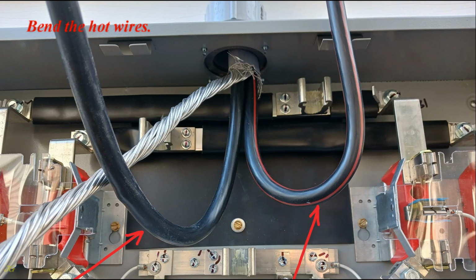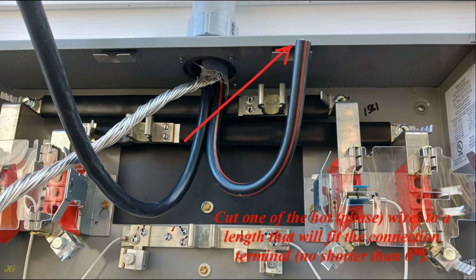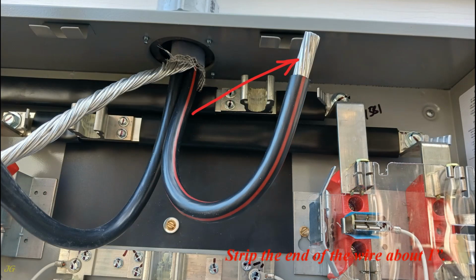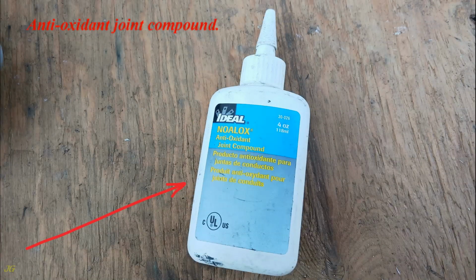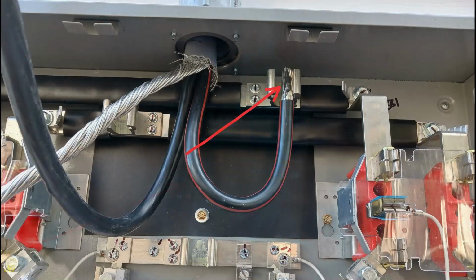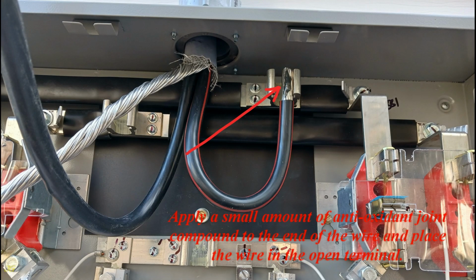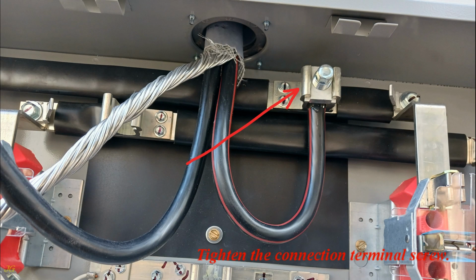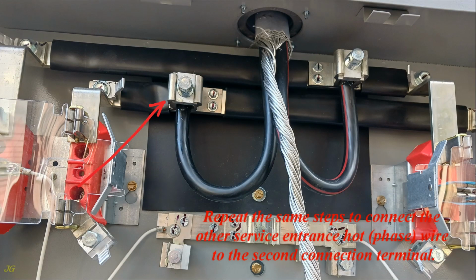Bend the hot wires. Cut one of the hot phase wires to a length that will fit the connection terminal, no shorter than 6 inches. Strip the end of the wire about 1 inch. Antioxidant joint compound. Apply a small amount of antioxidant joint compound to the end of the wire and place the wire in the open terminal. Tighten the connection terminal screw. Repeat the same steps to connect the other service entrance hot phase wire to the second connection terminal.